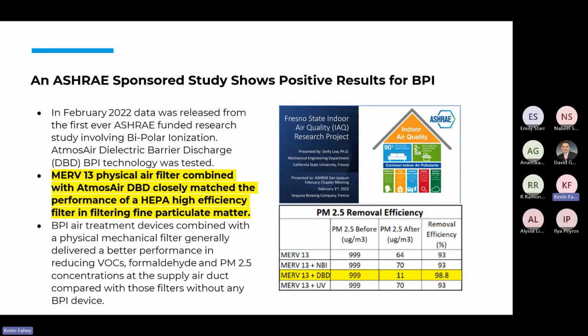ionization with filtration will give you a much better particle reduction in the space. And as a result, we find that when people install our system, they will reduce their MERV rating on their filters, which, as you know, will save energy and fan power, because the combination of the two technologies will be as good as potentially a MERV 11 with ionization giving you the ratings of a MERV 15 filter, without the pressure drop, without the cost of pushing air through the filters. Any questions? Continue on.